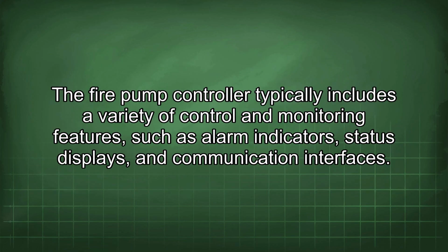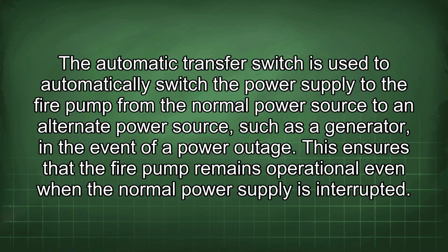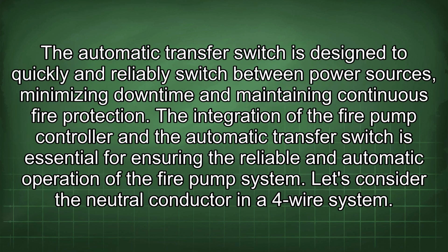The fire pump controller typically includes a variety of control and monitoring features such as alarm indicators, status displays, and communication interfaces. The automatic transfer switch is used to automatically switch the power supply to the fire pump from the normal power source to an alternate power source, such as the generator, in the event of a power outage. This ensures that the fire pump remains operational even when the normal power supply is interrupted. The automatic transfer switch is designed to quickly and reliably switch between power sources, minimizing downtime and maintaining continuous fire protection. The integration of the fire pump controller and the automatic transfer switch is essential for ensuring the reliable and automatic operation of the fire pump system.